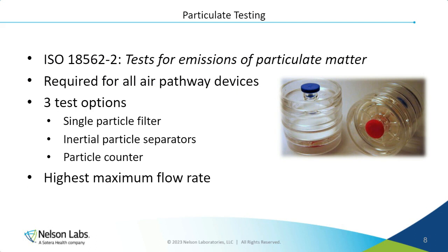As mentioned previously, particulates must be tested for all air pathway devices. There are three options: a single particle filter, inertial particle separator, or a particle counter. These particulates are tested by air being passed through, or through and around the device, and then being collected and ultimately counted. This air must be of a certain flow rate and temperature. Particulate testing requires the highest clinically relevant flow rate, or the highest flow rate for which the medical device may be set. This high flow rate must be used when sampling, as it is seen as a more worst case scenario. Of this air that has been sampled, particulate matter 2.5 and particulate matter 10 is then analyzed and taken into account within the toxicological risk assessment.